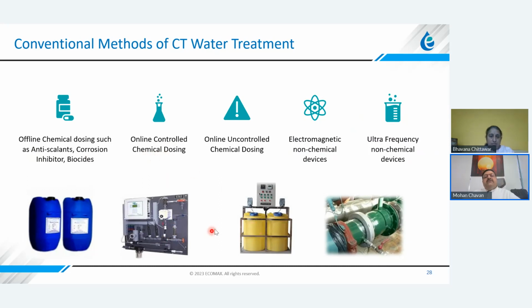The third method that is used is uncontrolled online chemical dosing. So you will have tanks like this, and then you have the metering pumps. You have a small control panel to control the operation of these pumps. But here these dosing pumps will operate continuously and pump the chemicals into the cooling towers. Then we have electromagnetic non-chemical devices and ultra-frequency non-chemical devices, which are not proven to be very effective when it comes to the applications.